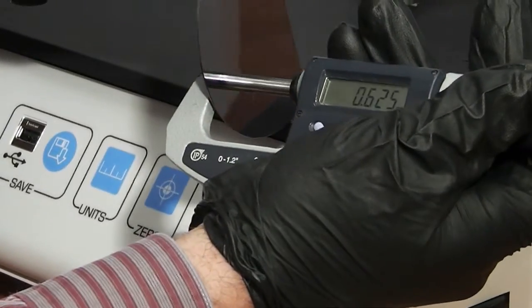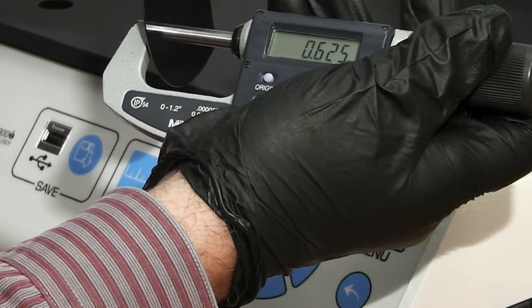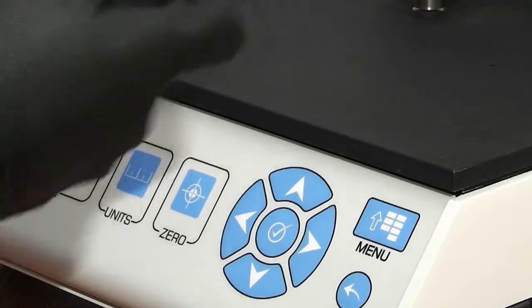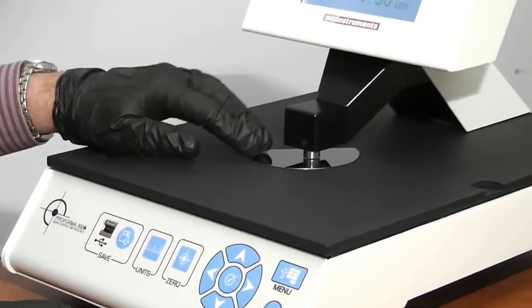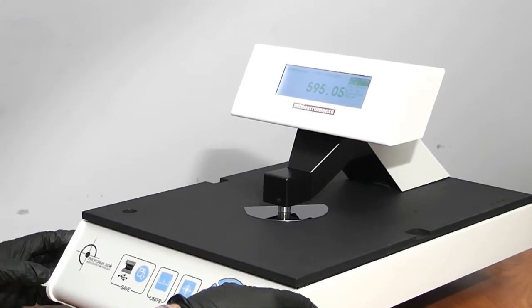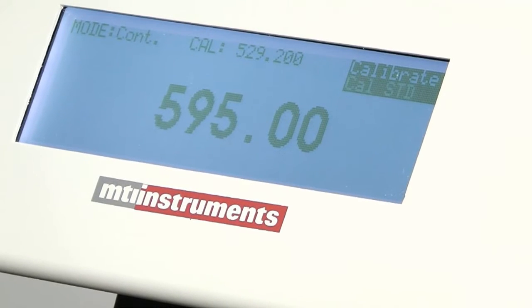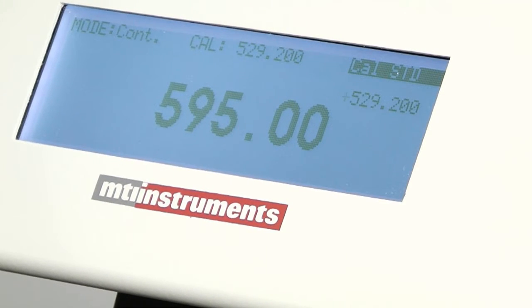So the way we do that is we either have a standard that we know the thickness, or we get a micrometer, and we measure a sample. In this case, we're seeing 625 microns. All right. We slide that under here. We go back and we do a quick calibration at 625 microns. So we change that to 625, and we get a zero in there, 625 microns, enter.